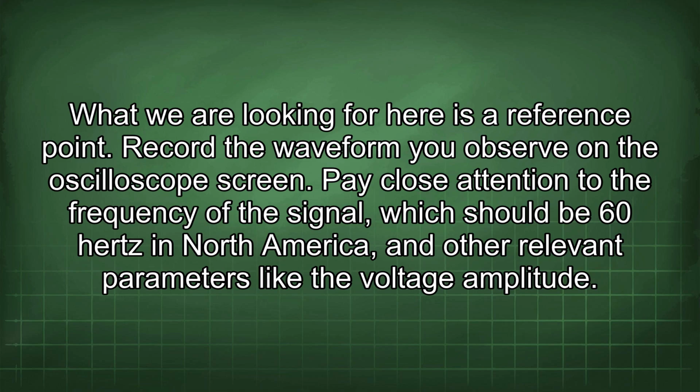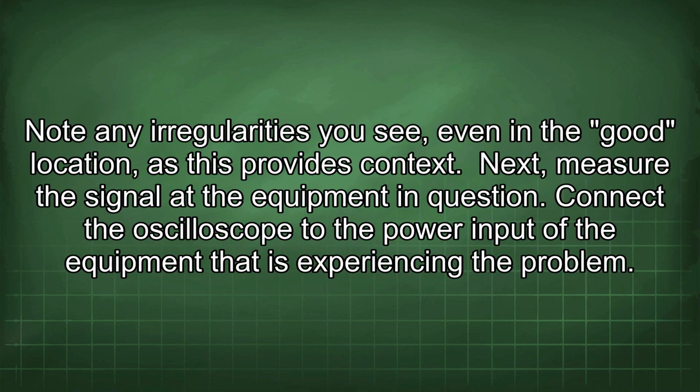Pay close attention to the frequency of the signal, which should be 60 Hz in North America, and other relevant parameters like the voltage amplitude. Note any irregularities you see, even in the good location, as this provides context.